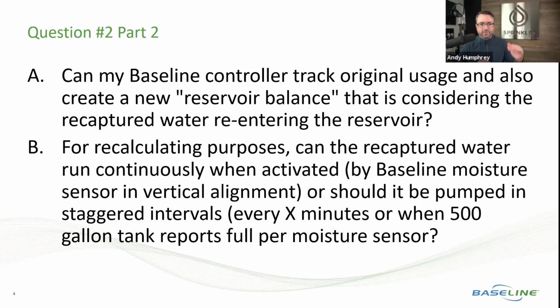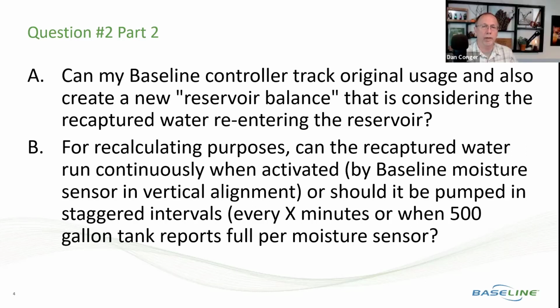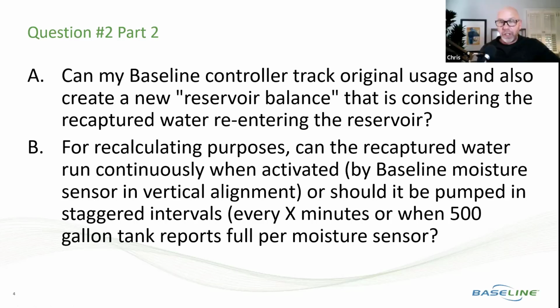You just have a wider range. With a sensor, you have 18 inches. With a pressure transducer, you have the entire depth of the tank. You could look at quick view and see the tank is 50% full, even though it won't react until it gets to 10% empty or 10% full. And you can equate that amount of volume in the tank based on the depth, or the pressure, to the number of gallons available at that pressure level.